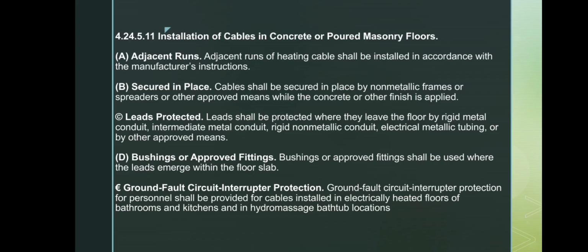When heating cables are installed in concrete or poured masonry floors, adjacent runs must follow the manufacturer's spacing instructions. The cables must be held in place using non-metallic frames, spreaders, or other approved supports while the concrete is poured. Where leads exit the floor, they must be protected using conduit, metal or non-metallic, and proper bushings or fittings must be used where the leads emerge.